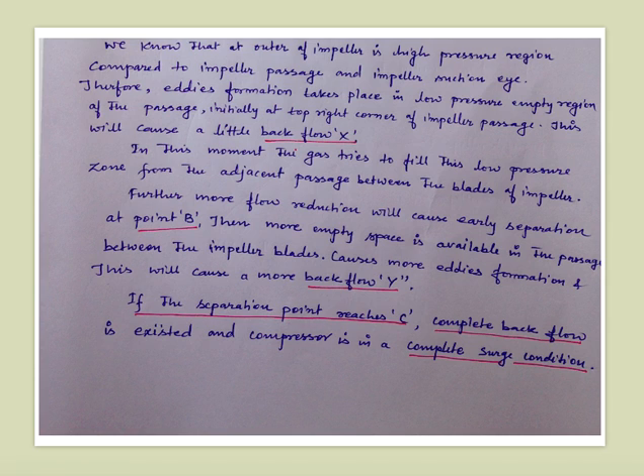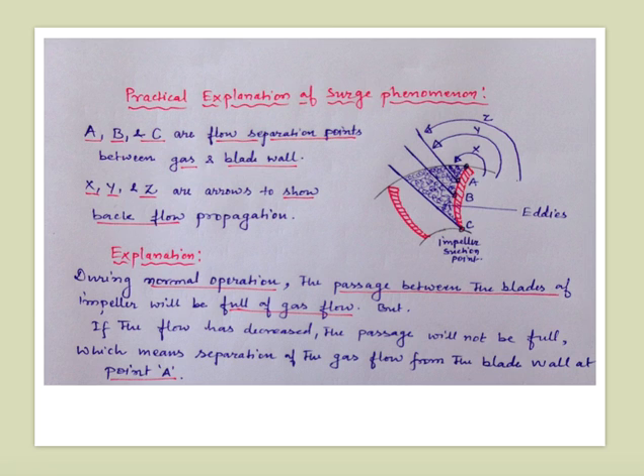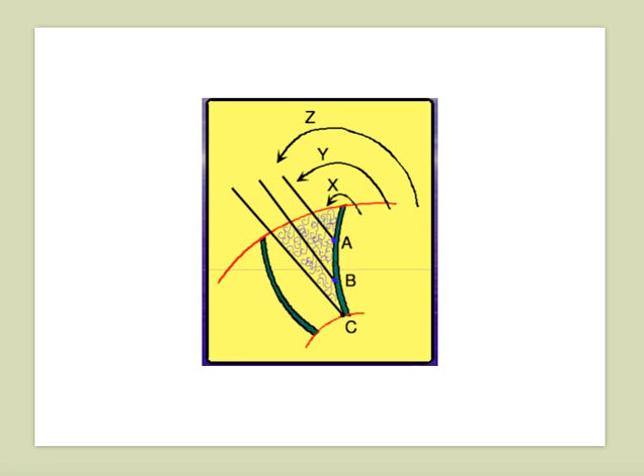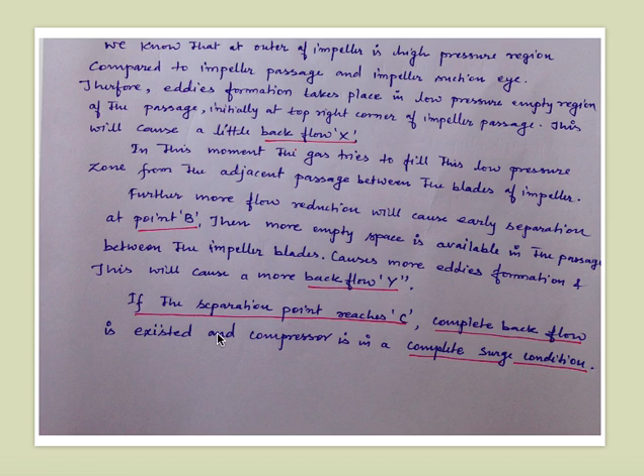If the separation point reaches C, the empty space where eddy formation is occurring and the low pressure region is even bigger. The backflow is now very significant. At point C, complete backflow exists and the compressor is in complete surge condition. When the complete backflow condition starts on the impeller blades due to reduced suction flow to the compressor, this is the complete surge situation. That covers all the concepts of centrifugal compressor surge — thanks for watching.